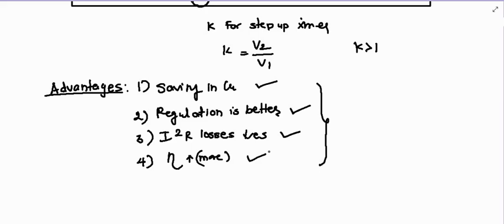In your two winding transformer, both windings are electrically separated and magnetically coupled, right? Here both windings are magnetically coupled as well as not electrically separated, as one winding is forming part of the primary as well as the secondary. So there is higher risk of serious electric shock when it is used in high voltage circuits. Then why are we using auto transformer? We are using auto transformers for lower voltage rating.